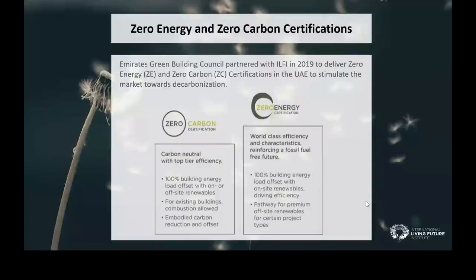According to the definitions, a zero energy building is a building that generates 100% of its energy needs through on-site renewable energy. Off-site renewables can be considered in some cases, such as where there is no interest from the project owner to install PV if a tenant is considering a zero energy certification. Off-site renewables can be considered for buildings with high baseline EUIs, or in cases where there are grid limitations. A zero carbon building requires also meeting 100% of the annual energy demand through renewable energy. However, it provides more flexibility in terms of using off-site renewable energy.